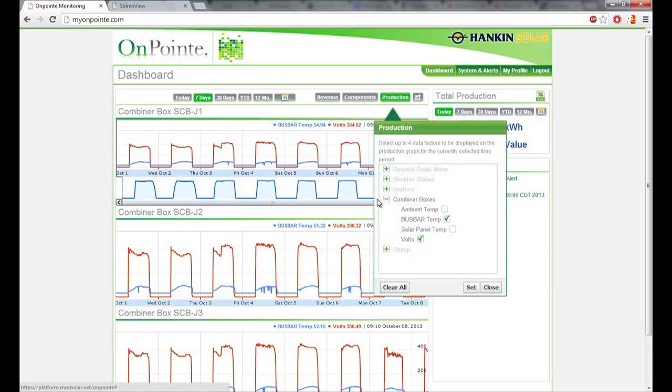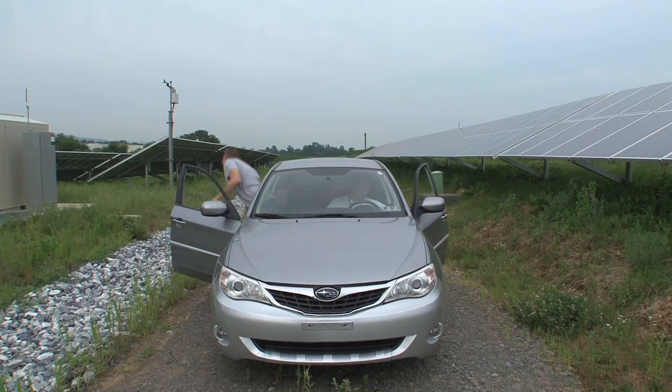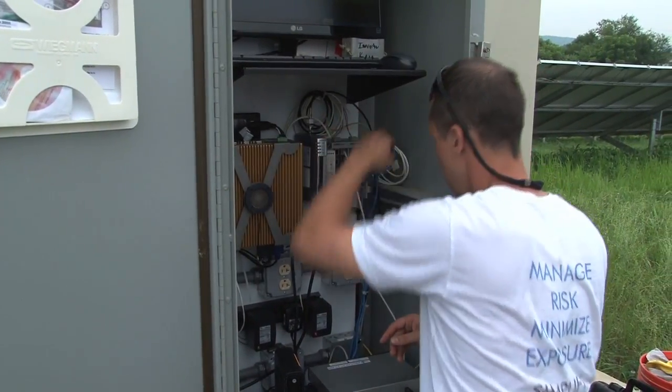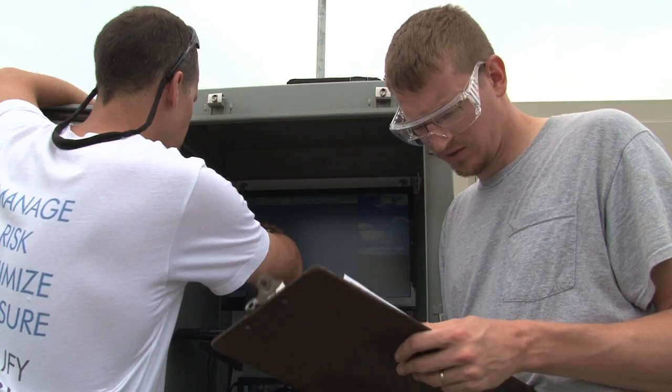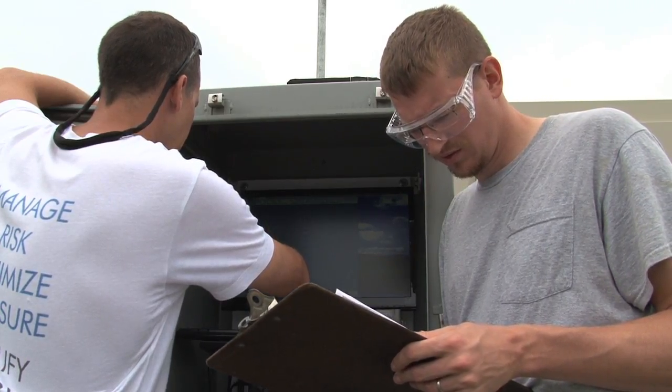Before the visit, online monitoring systems should be checked weekly. Just prior to the visit, you should check the monitoring system for errors, alerts, and issues. Upon arrival at the site, the crew reviews the site-specific safety plan, and any known trouble spots recognized as problems in the past should be checked right away. On-site monitoring units should be checked as well. At this point, the crew may address any obvious issues before starting their overall assessment.